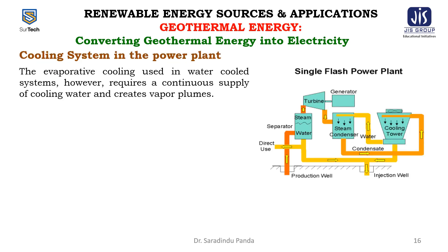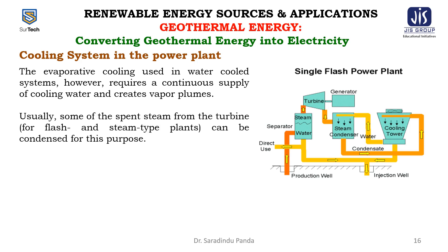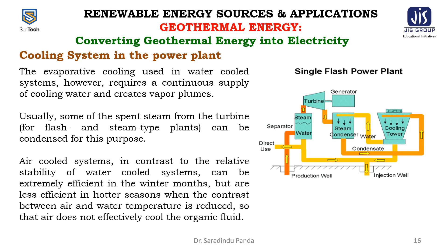Evaporative cooling used in water-cooled systems, however, requires a continuous supply of cooling water and creates vapor plumes. Usually, some of the spent steam from the turbine for flash or steam type plants can be condensed for this purpose. Air cooling systems, in contrast to the relative stability of water cooling systems, can be extremely efficient in winter months but are less efficient in warmer seasons, when the contrast between air and water temperatures is reduced and the air does not effectively cool the organic fluid.